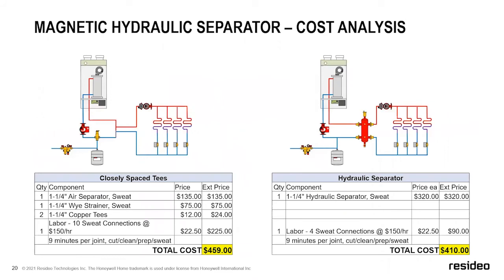Now, one thing I do want to highlight is the hydraulic separators are dramatically more expensive than closely spaced tees. But I want to expand on that, because when you break it down, they're really not. When I was on the distributor side selling systems, I would have this conversation fairly regularly, because people are used to seeing 1.25 inches. In this example, I'm using 1.25 inches, and I've mocked up some rough numbers here. You'd see an air separator that's maybe $135 and a set of closely spaced tees that's maybe $20. So people will come to me and say, well, why would I buy a hydraulic separator at, in this example, $320, when an air eliminator and closely spaced tees are only $150?